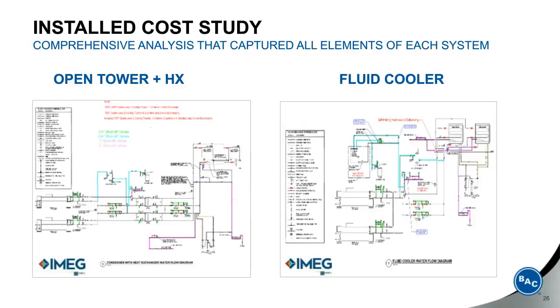Okay, so IMEG created designs for both the chiller and the water source heat pump systems in Chicago and Dallas. Firstly for an open tower and heat exchanger, and then repeated the exercise using a fluid cooler, identifying in great detail all the necessary elements to allow for an exhaustive comparison rather than just a general approximation of the requirements of each system, as can be seen here in these schematics. Now, you can't see the specifics, but it's apparent that the designs are built as if for a real job. So every element has been taken into consideration here, and these are as accurate as we can get with regard to how a system might be built to meet the requirements as detailed on the slide.